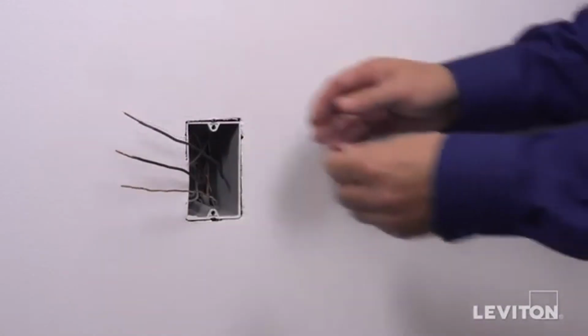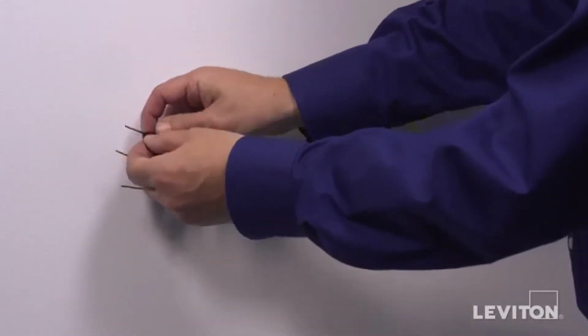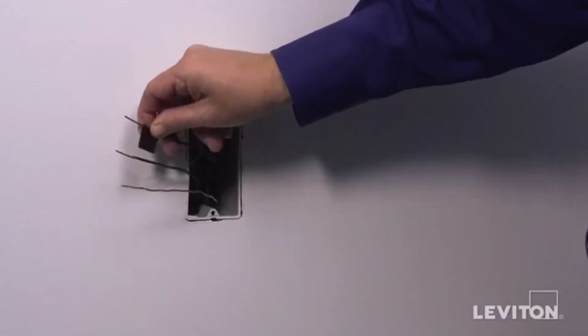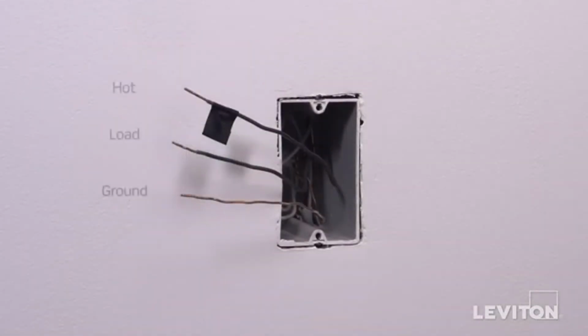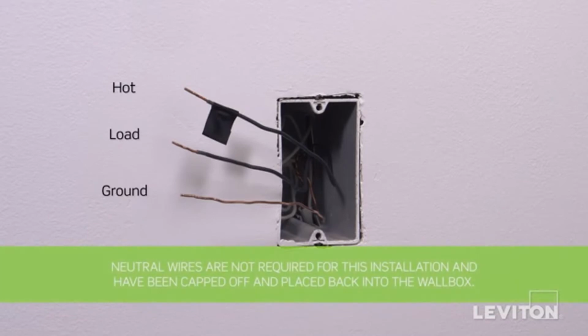Use a small piece of electrical tape to label the hot wire. In this example, there is one black wire which is the hot, a black wire which is the load, and a bare copper wire which is the ground. Keep in mind, the color of the wires may vary. The hot wire may be black or red. The ground wire may be green or bare copper. If you're unsure, contact an electrician.